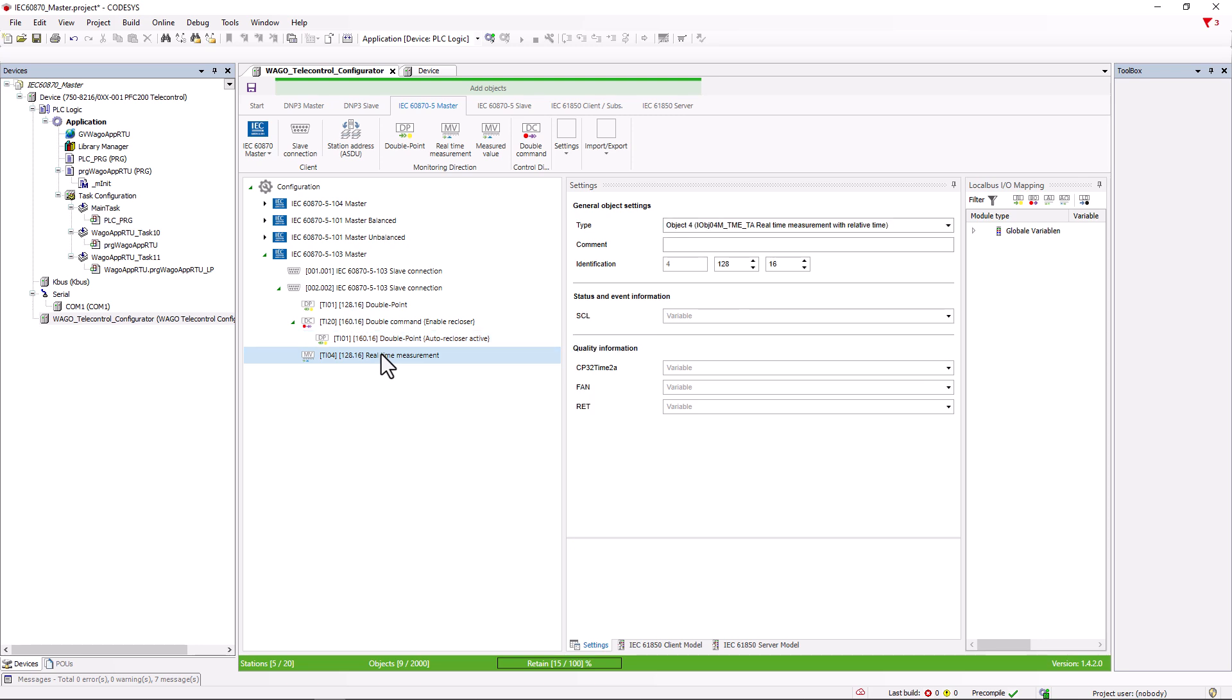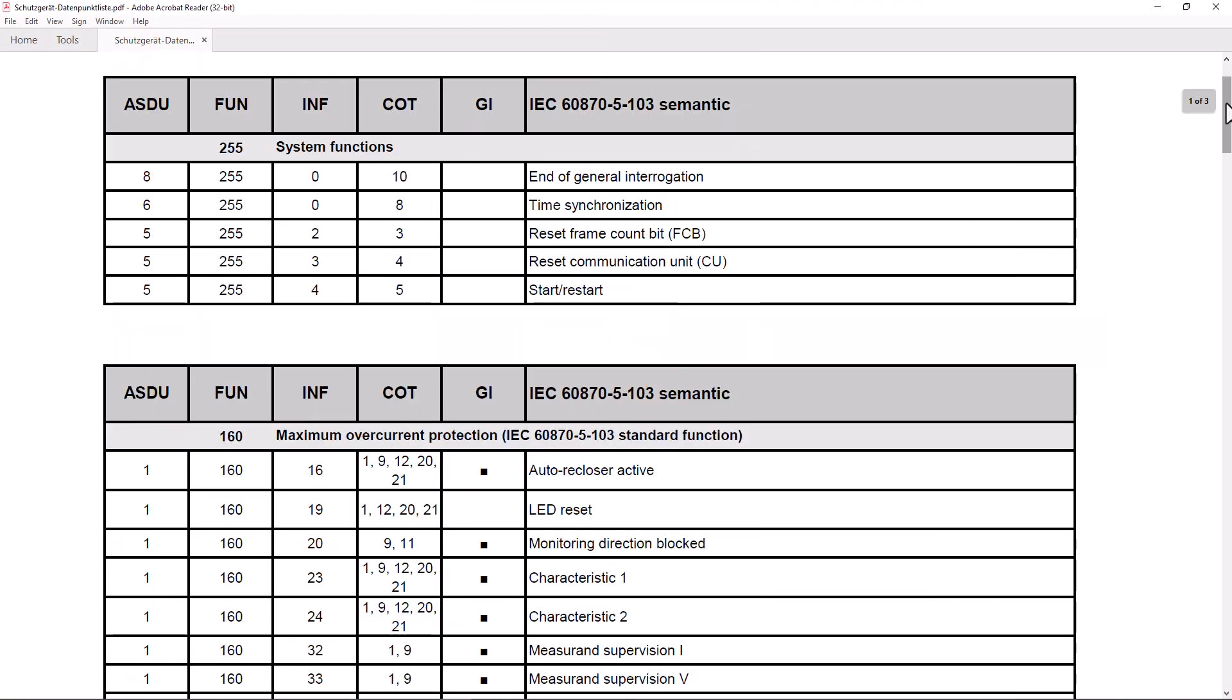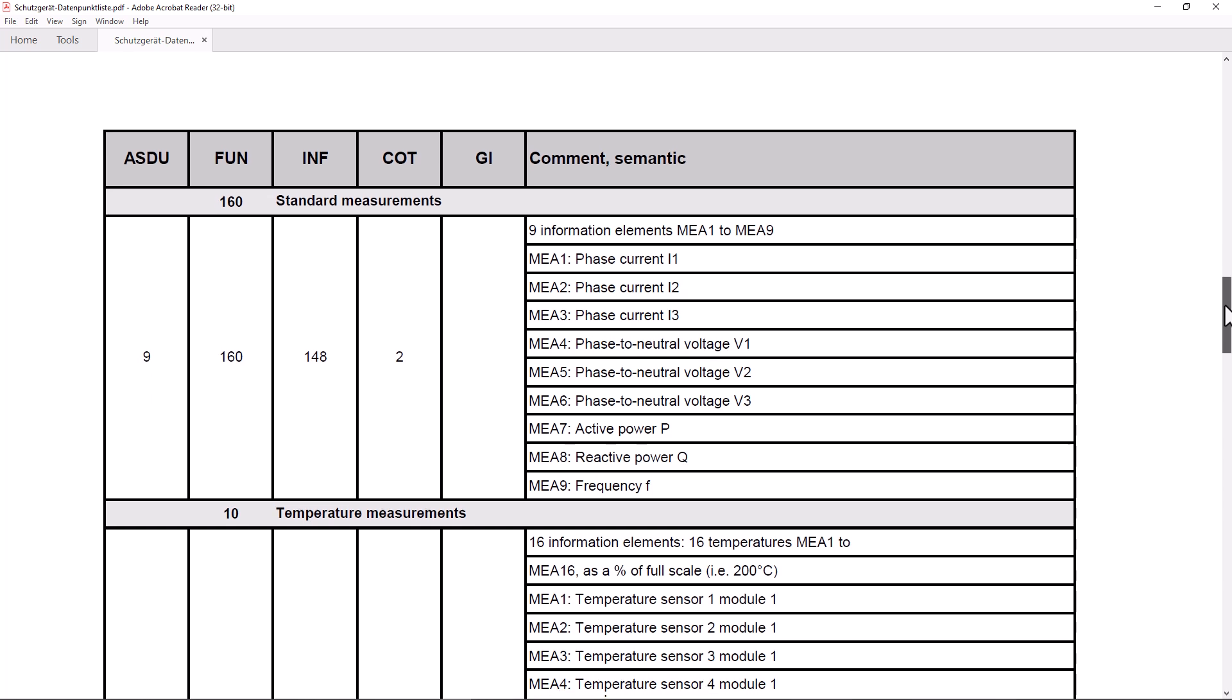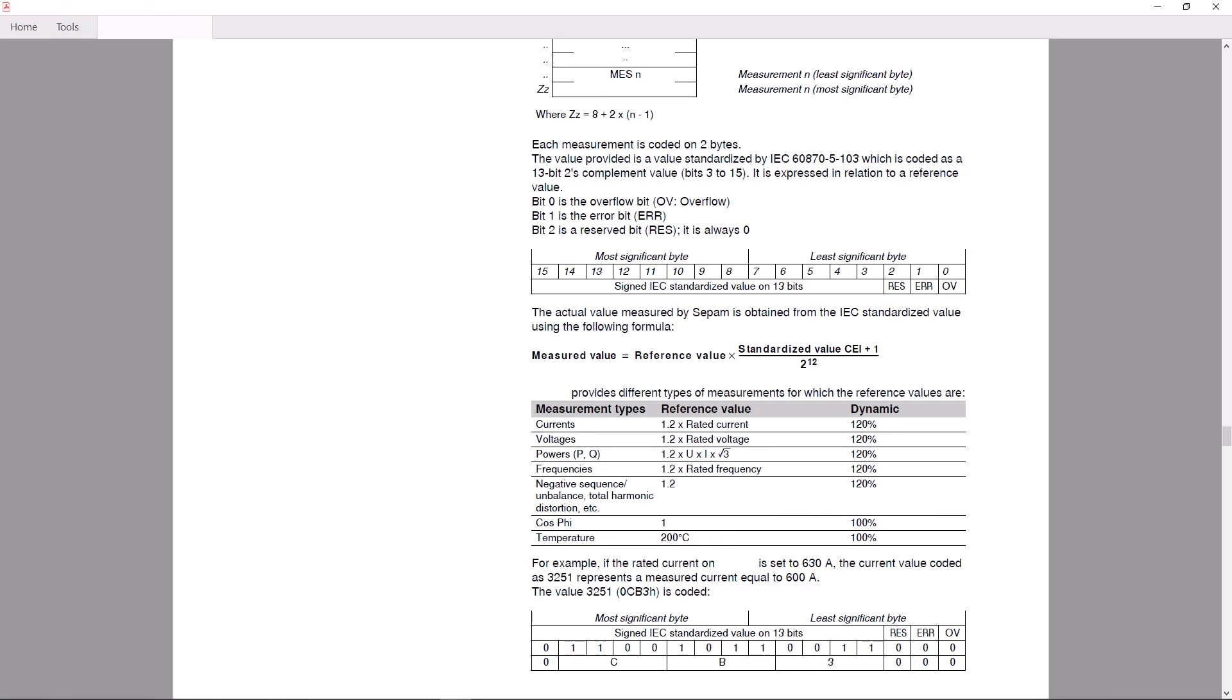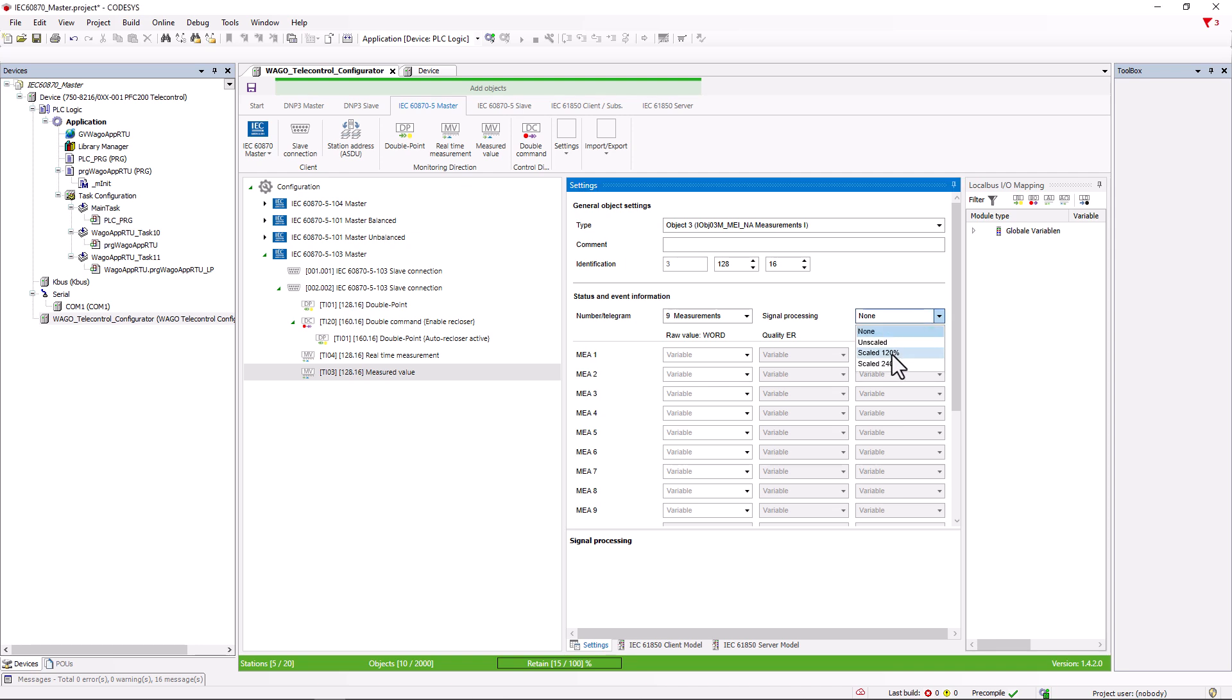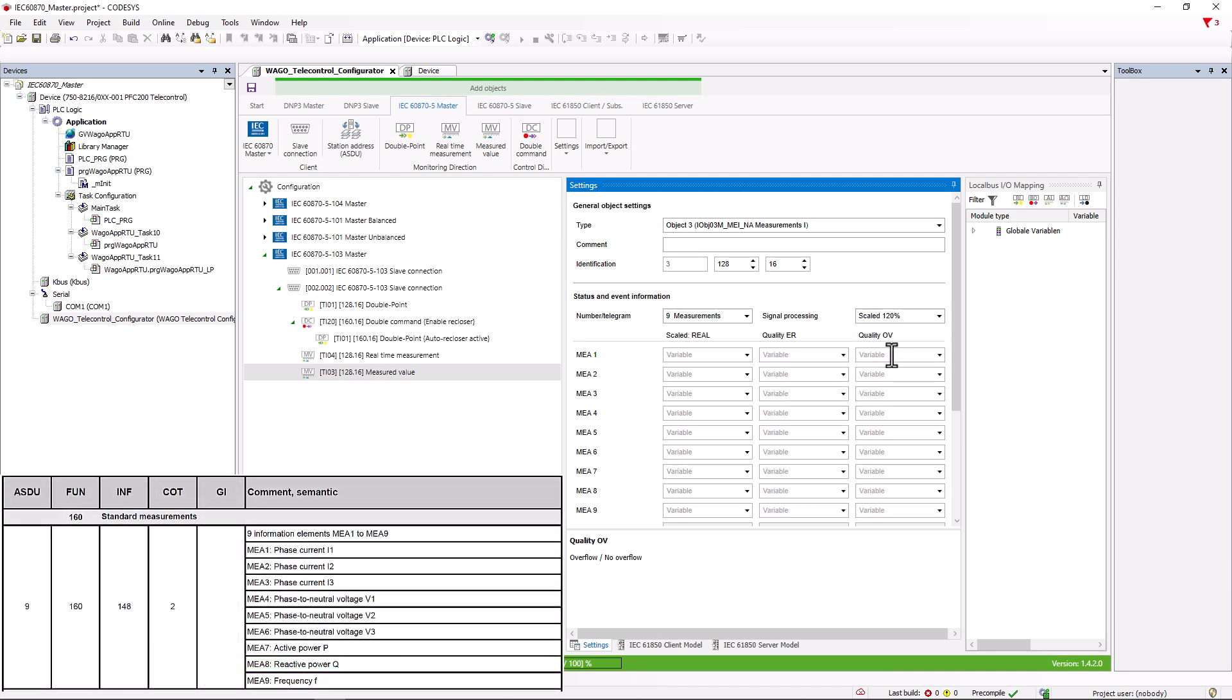The data point next to it is also interesting. Measured value, which allows up to 18 measured values to be recorded simultaneously. In the protection device manufacturers list, under measured values we find the following list, three measurements of the phase currents, three measurements of the voltage of the three phases, the active power, the reactive power and the frequency. Further on in the technical documentation, we also find a note that these measurements are scaled to 120%, which we need to set under signal processing. A measured value package of nine measured values, which we create here and to which we assign variables.